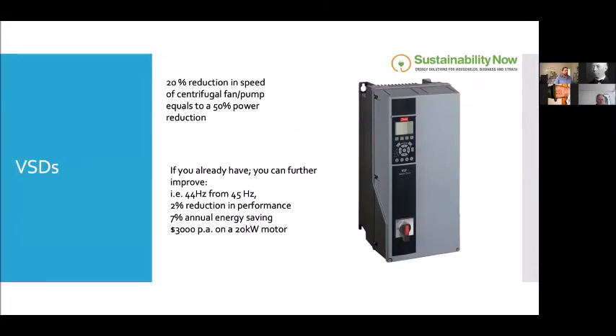VSDs again, Vasilius has talked pretty extensively about this. So for a centrifugal pump or fan, reducing the speed of that pump or fan, or the motor that powers it, by 20% will result in a 50% reduction in power consumption. It's not a linear relationship, it's a cubic relationship.